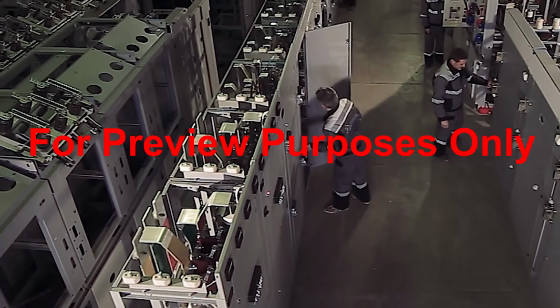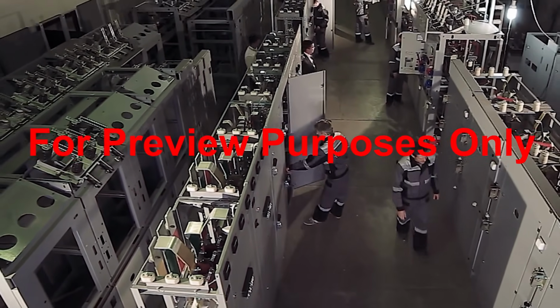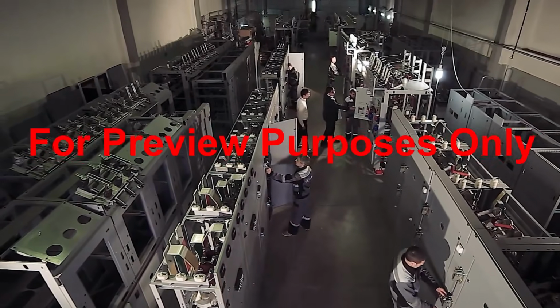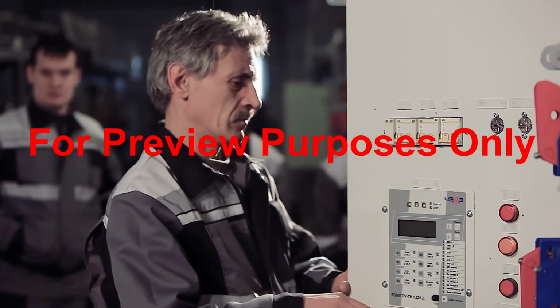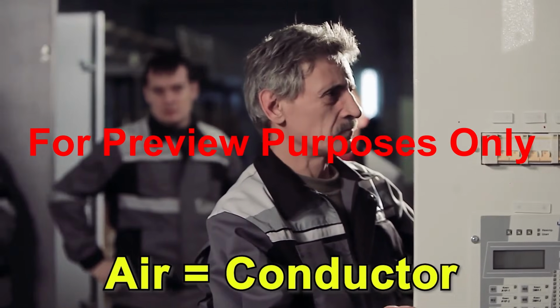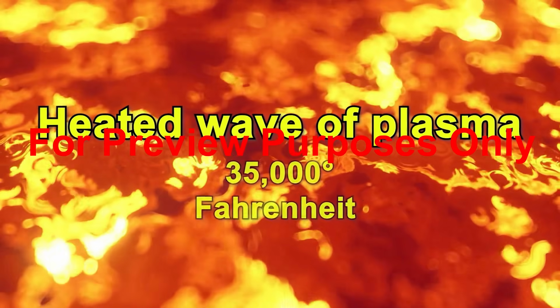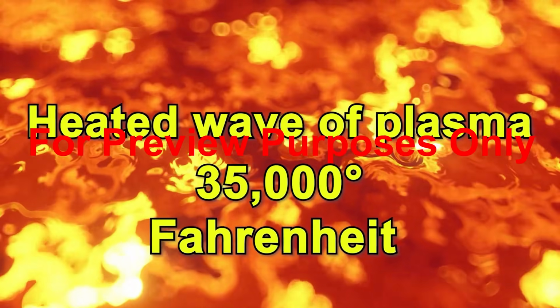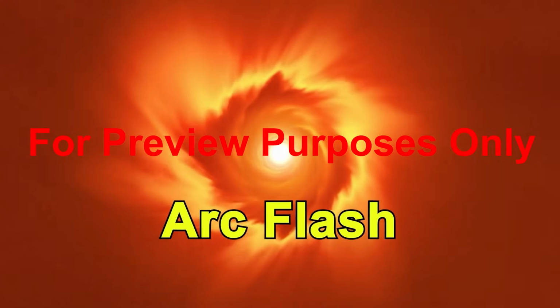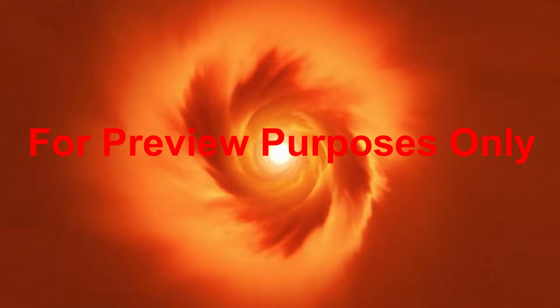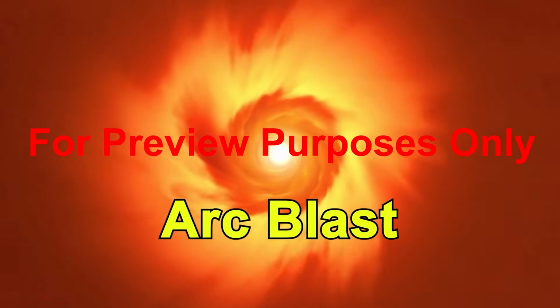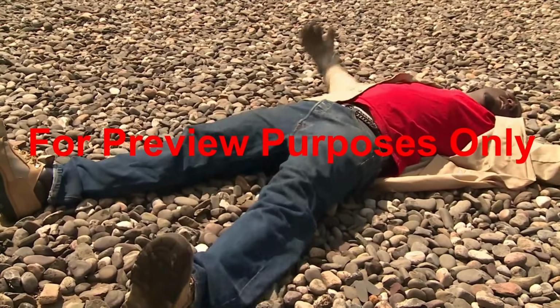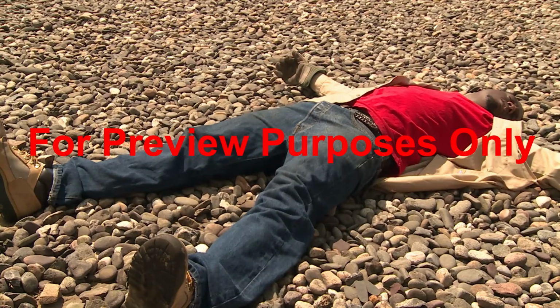But as serious as these injuries are, they are mild compared to what can happen during an arc flash event. This is an electrical explosion that occurs when air becomes the conductor of electricity, which can cause a heated wave of plasma that can be as hot as 35,000 degrees Fahrenheit. The light and heat from the explosion is called an arc flash, while the pressure wave that follows is called an arc blast, and it can be powerful enough to knock you off your feet.